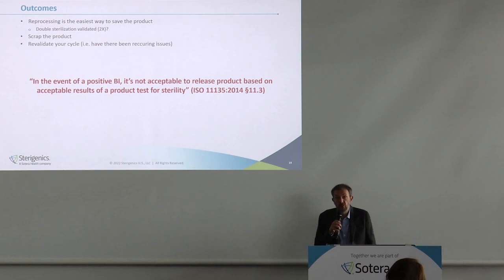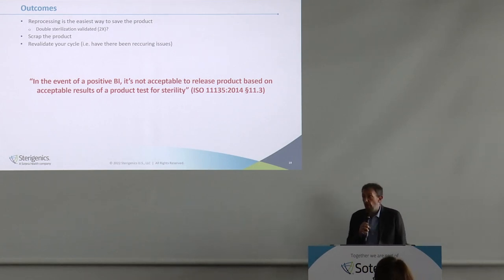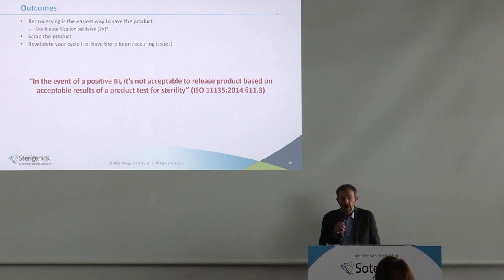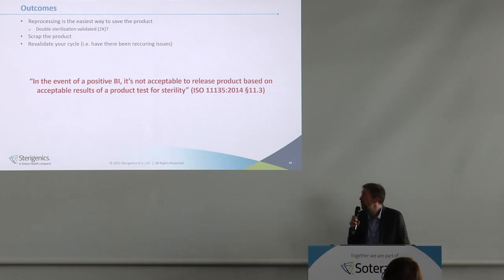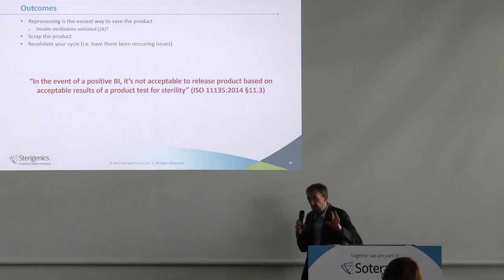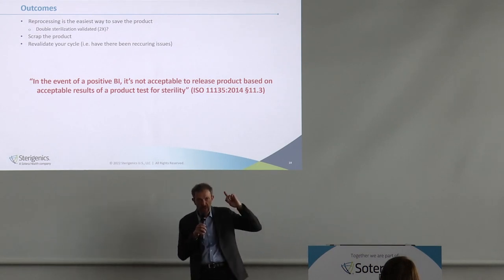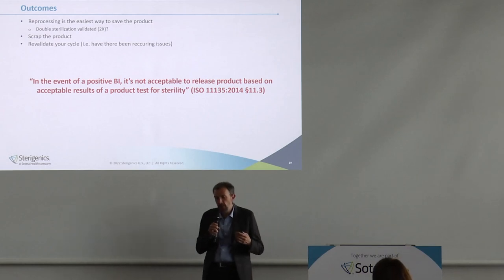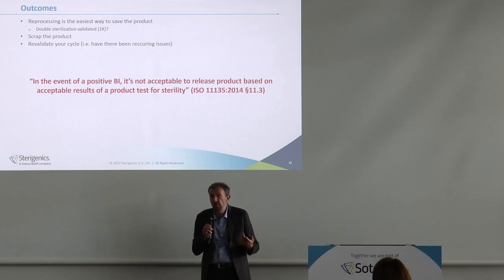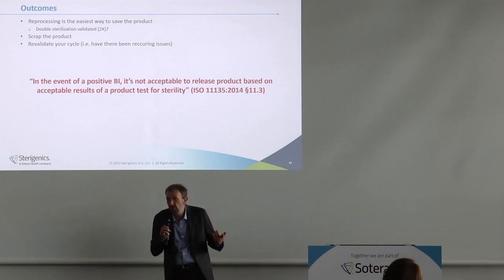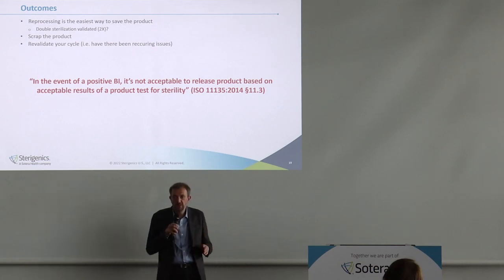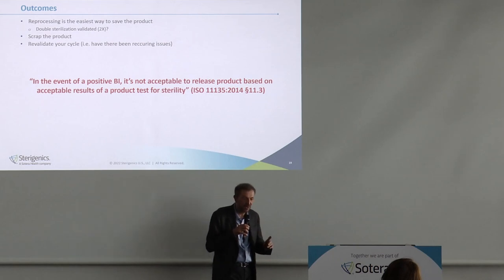If you have validated reprocessing, you reprocess the load. If no root cause was assigned and it was just bad luck, you can reprocess without concern. Or unfortunately you may have to scrap the load if it's not reprocessable. If the failure puts the validation into question, there is no other way than performing a full revalidation. It is written in the standard — black and white — that it is not possible to release a load with a positive BI. You cannot perform product sterility testing to justify release: to validate a SAL of 10⁻⁶ you would need to test a million products, which is not feasible.